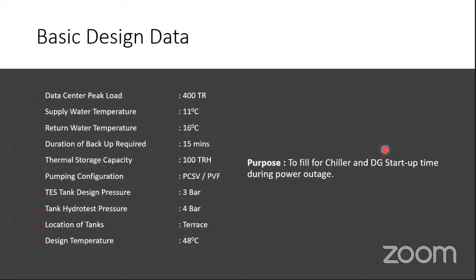Okay, we will now understand the stratified thermal energy storage system design in a different application, that is emergency chill water supply. This is mostly used in data centers. It's very popular these days, and the design of this has different considerations. So what is the basic design data here? We could actually talk in terms of a data center application, to be very specific, in which the purpose is to fill for the chiller and DG startup time during power outage.